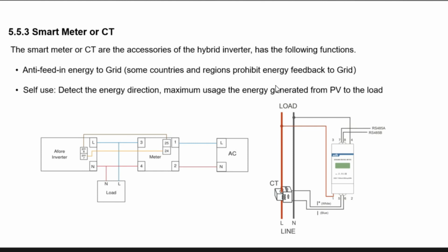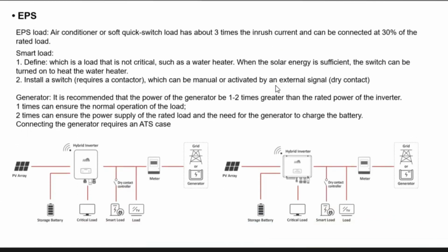The smart meter and the CT actually have the same function. One is anti-feeding energy to the grid. Another is to detect the energy direction, for maximum usage of the energy generated by the PV for local load. For the single phase inverter, we provide two different smart meters. One is a smart meter without CT. Another is for when the residential load is bigger than 10K, up to below 40K. This kind of application needs another smart meter with CT.